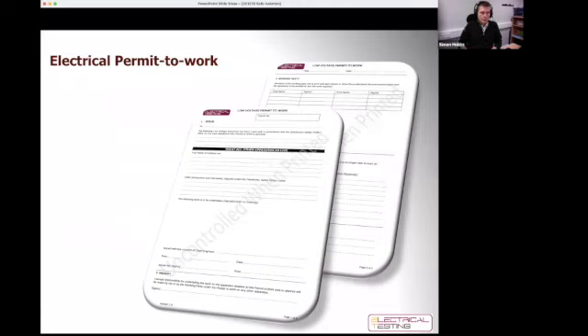But let's have a look at electrical permit to work with regards to 2 supplies. Whilst an electrical permit to work must be used for an HV, high voltage system, because it has to be made dead before it's worked on, obviously, they can be useful in certain low voltage situations, such as when we've got more than one source of supply. It is only an administrative document, so it isn't going to stop electricity flowing, but these permits are primarily a statement that a circuit or an item of equipment has been isolated and made safe to work on.